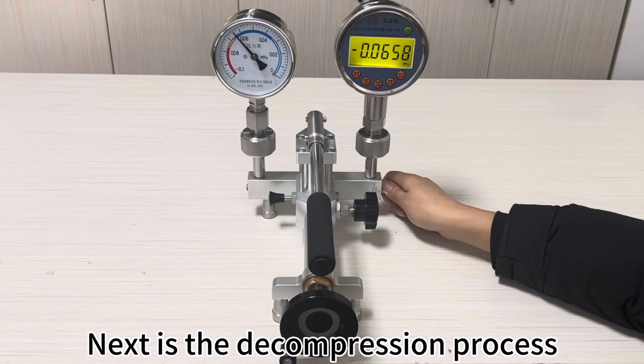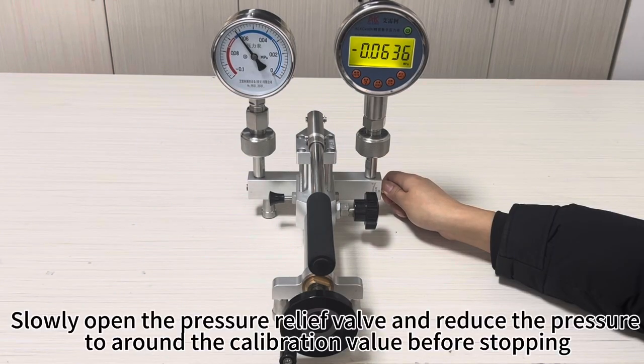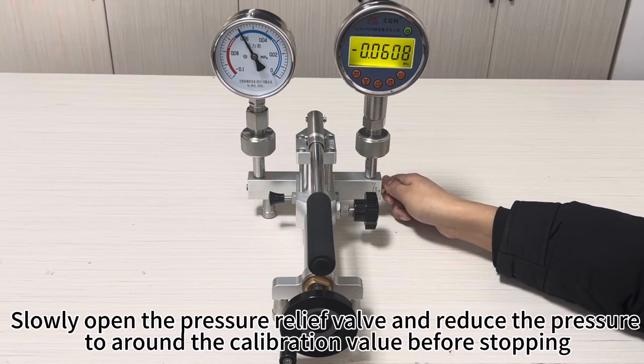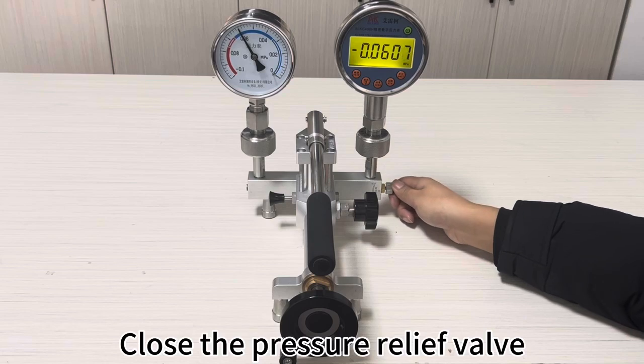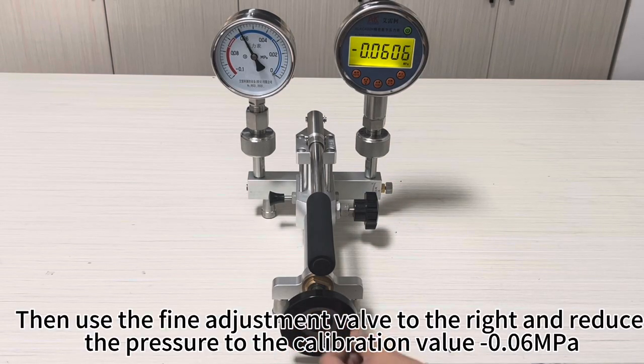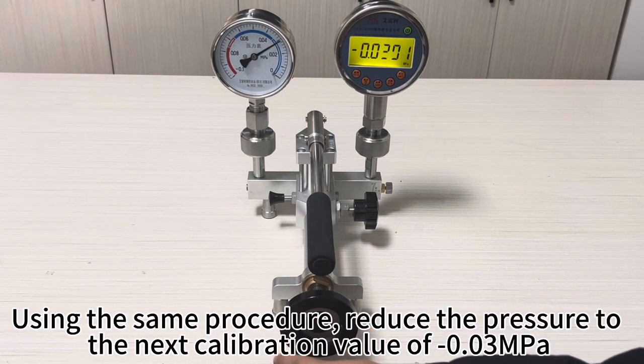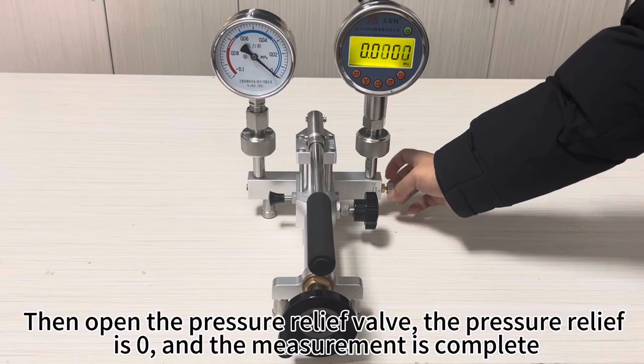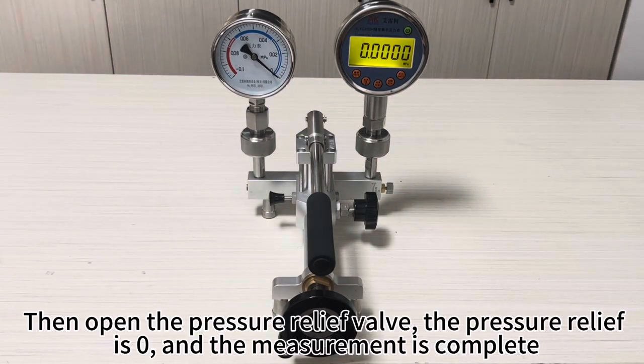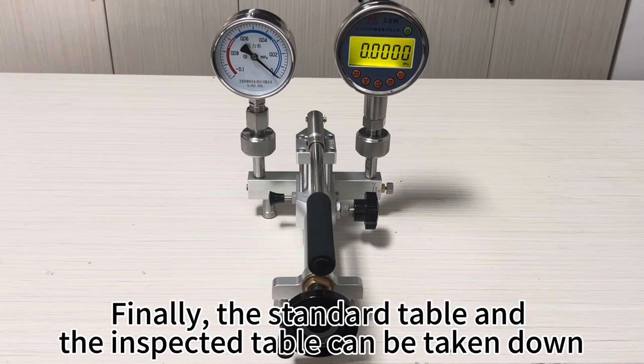Next is the decompression process. Slowly open the pressure relief valve and reduce the pressure to around the calibration value before stopping. Close the pressure relief valve. Then use the fine adjustment valve to the right and reduce the pressure to the calibration value of -0.06 MPa. Using the same procedure, reduce the pressure to the next calibration value of -0.03 MPa. Then open the pressure relief valve. The pressure reads 0, and the measurement is complete. Finally, the standard gauge and the inspected gauge can be taken down.